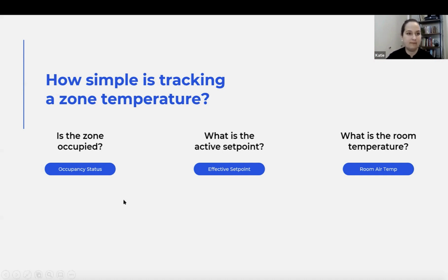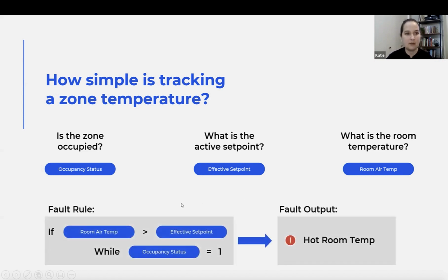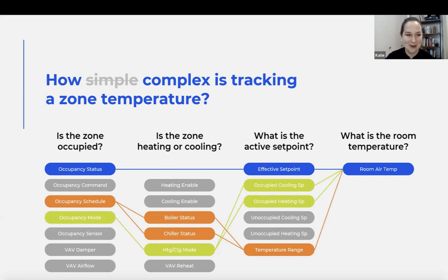So easy. Let's look at when the zone's occupied, what's my set point, and what's my room temperature. So I say when my room air temp is higher than my set point, when I'm occupied, I want to know. Easy, right? You just take that fault, you copy it, and you paste it all over campus in all of your zones, right? No. So you probably know this too. But in my experience across campuses, depending on when the building was designed, who did the programming, who did the design, what calling something occupied is not always the same. In some buildings, you might have an occupancy status point. In other buildings, you might just have to look and see if your VAV damper is open, and then you know it's occupied. There are different things that would indicate that your zone is occupied.